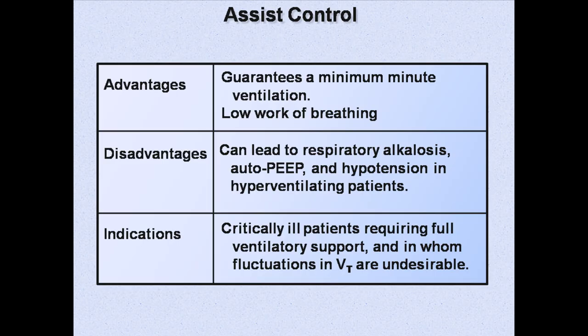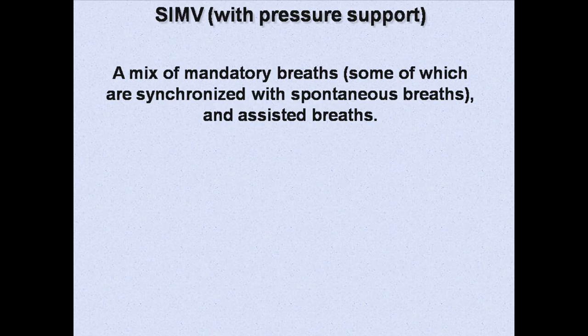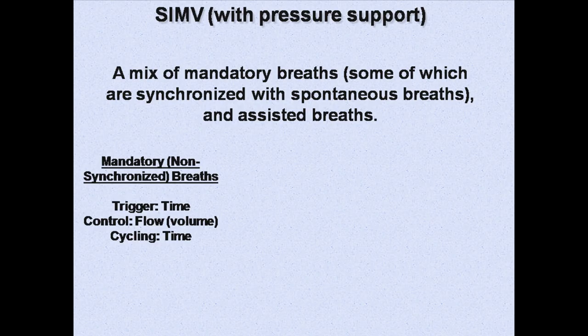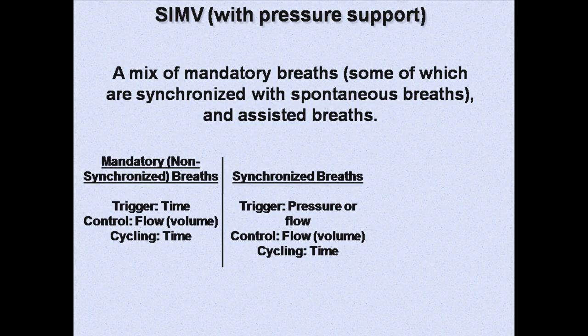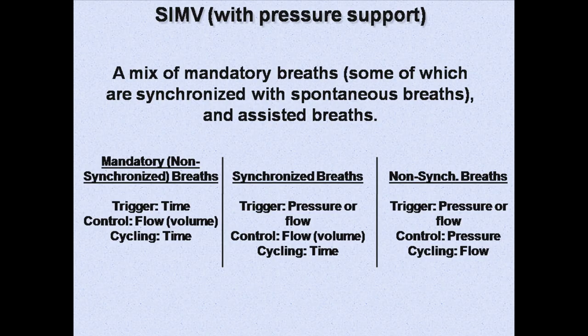Let's now talk about SIMV. Although SIMV can be used without pressure support, it is very rarely done, so the following will assume that pressure support is being used. SIMV is a mix of mandatory breaths — some of which are synchronized with spontaneous breaths — and assisted breaths. The mandatory non-synchronized breaths are time triggered, flow controlled, and time cycled, while the assisted breaths synchronized with the mandatory breaths are pressure or flow triggered, flow controlled, and time cycled. The non-synchronized assisted breaths are pressure or flow triggered, pressure controlled, and flow cycled, and are only partially supported breaths.